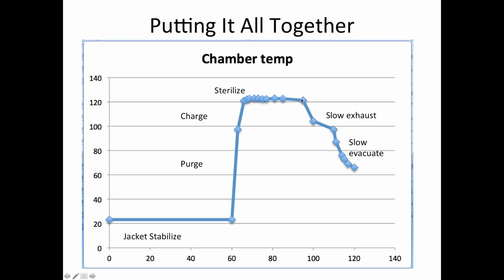And when we reach the end of our sterilization cycle, which in this case is 20 minutes, then we begin to get into the slow exhaust and the slow evacuate cycles to bring the temperature back to close to normal and bring the pressure inside the autoclave back to atmospheric.